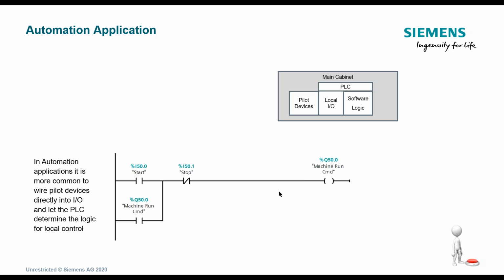With this in mind, on the logic side now that we're on the software side, we want to look at the logic and see how we can minimize that logic. And what I mean by that is that this simple circuit right here, this is my interlock or my maintain, because this push button might be a momentary push button to start the motor, but you want the motor to continue to run. So you have to have some type of interlock that locks that motor, and it continues to run until somebody presses stop. So this is your sealing circuit or your interlock or your maintain contact for that.